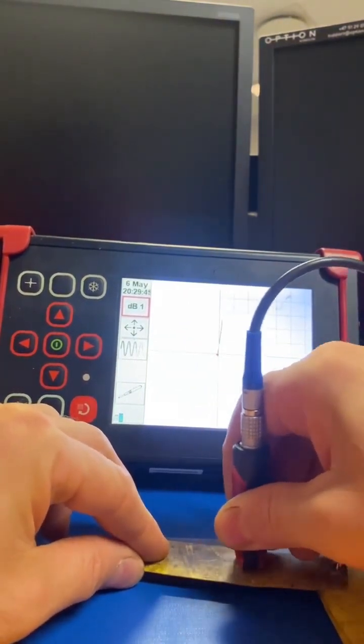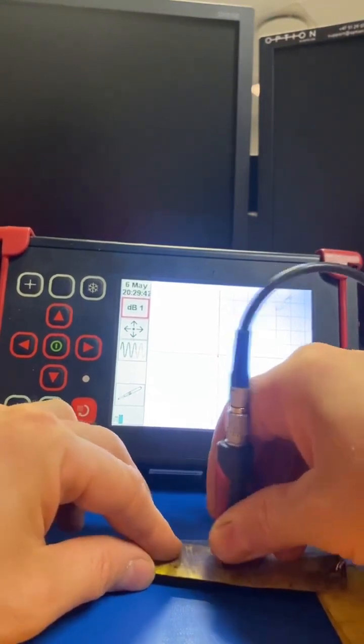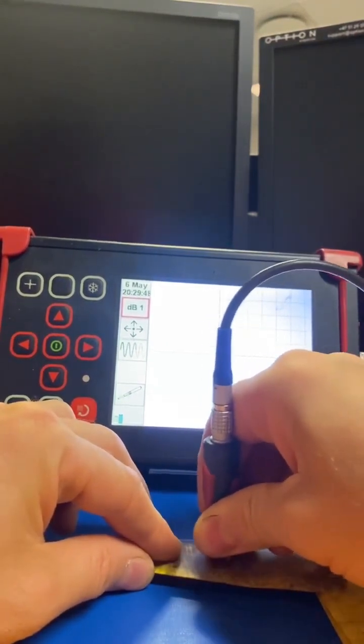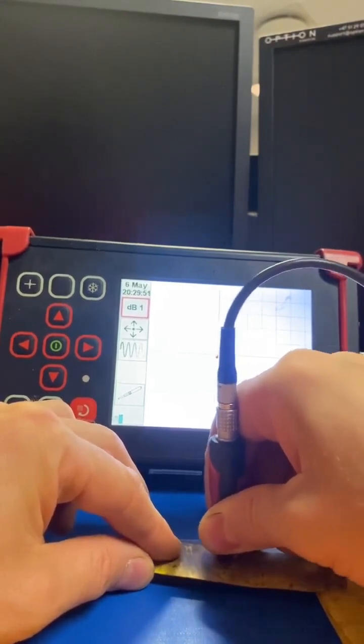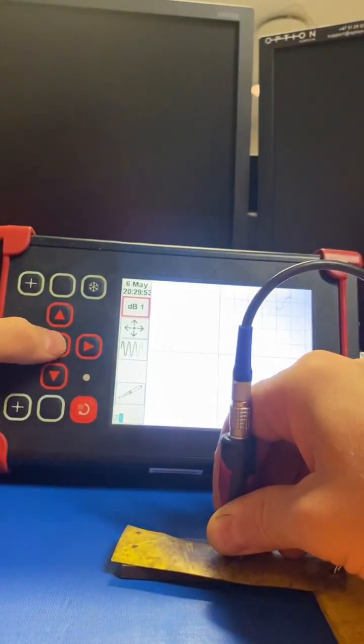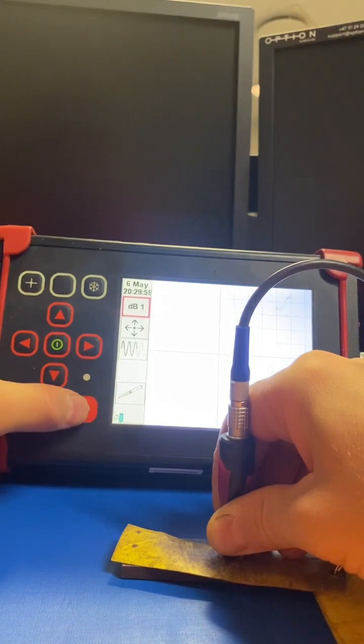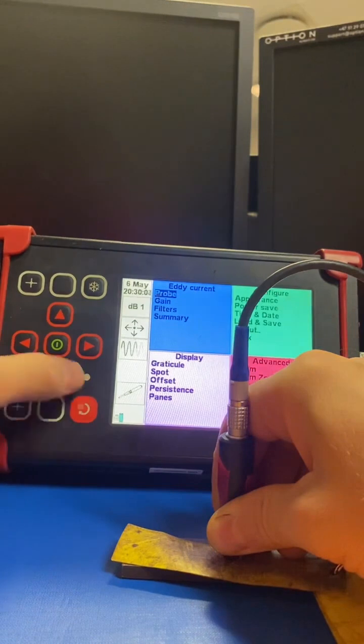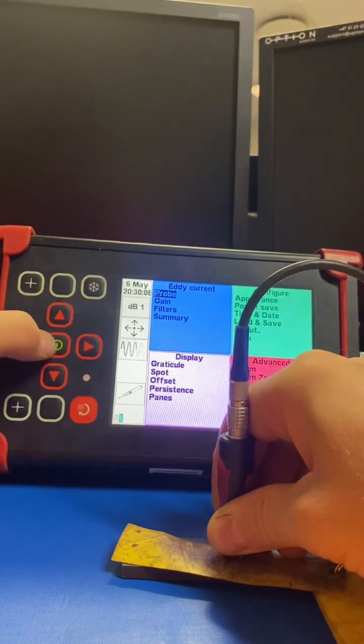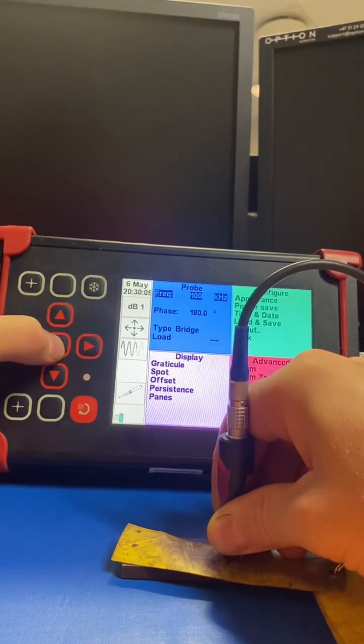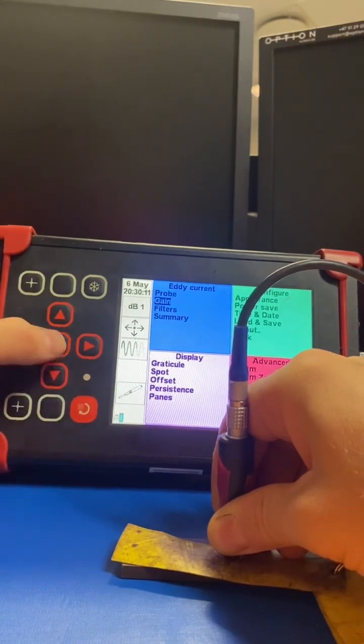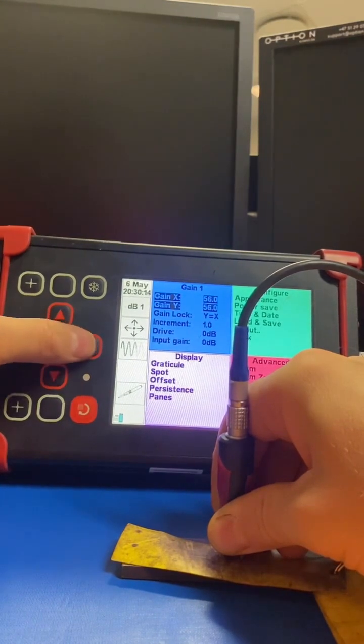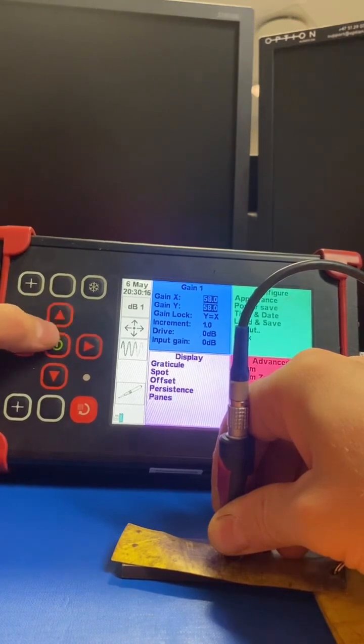The visual display currently indicates that we are operating at approximately 70%, suggesting there's still room for improvement. We have the capability to increase the gain to achieve a fuller signal. We can go to the menu like this. We can go on a probe. No, not on a probe, on the gain. And put 58.